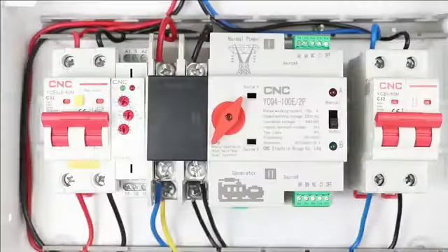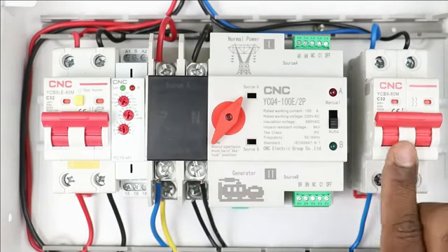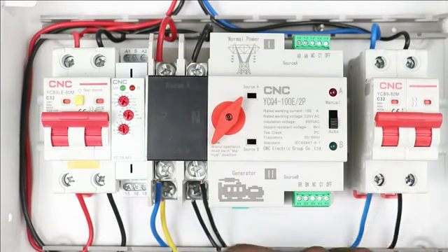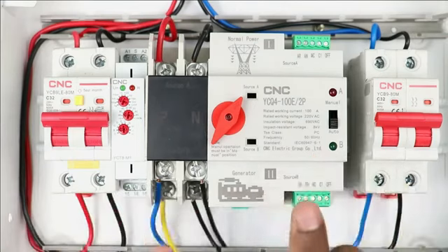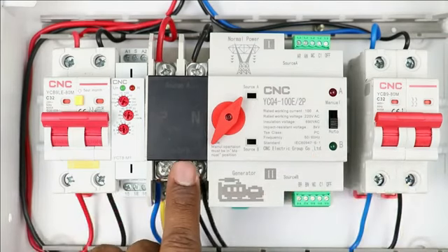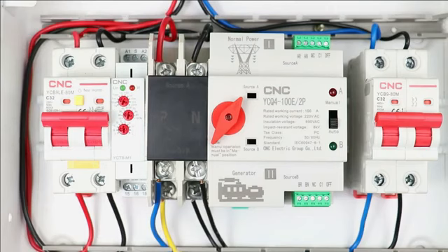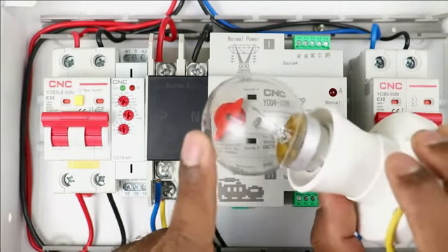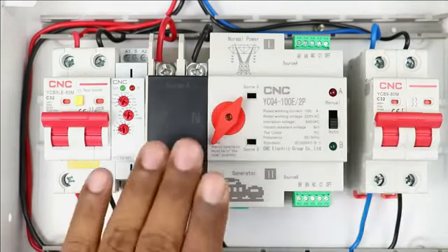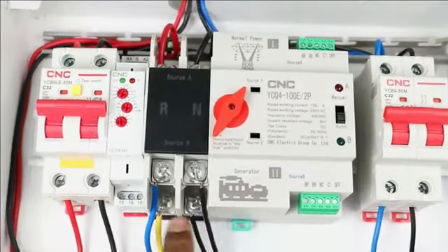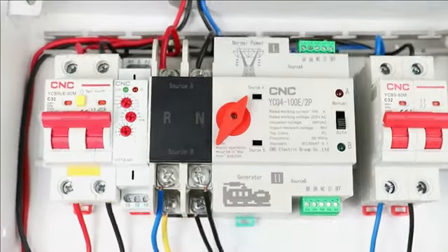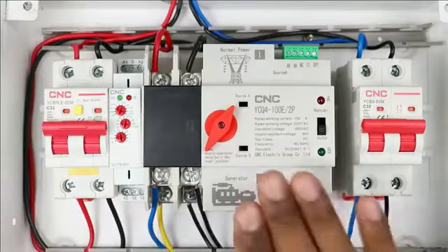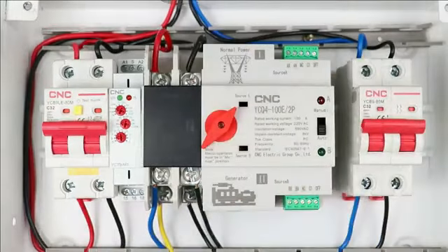After this, from the MCB for UPS or generator, connect two wires at output terminals and connect the other ends of the wires at source B terminals of ATS. After that, whatever the load may be, for now I am using a lamp. The power supply to this lamp will be supplied through the terminals of ATS. You can see these lower side terminals. From here, power will be supplied. For this ATS, only this much power wiring is required.